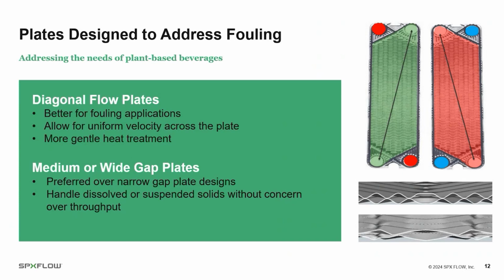First, there's diagonal flow plates. These plates are better for fouling applications. They allow for more uniform velocity across the plate, avoiding the high fouling tendency on the low velocity side of a traditional vertical flow plate design, resulting in a more gentle heat treatment along the entire product path.